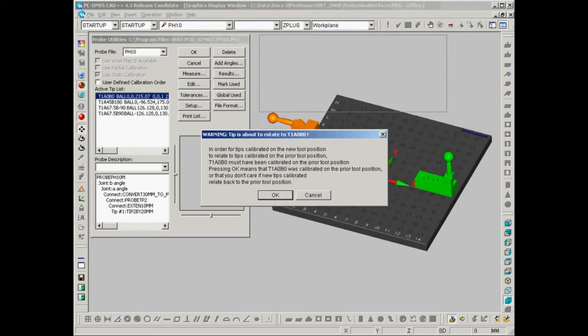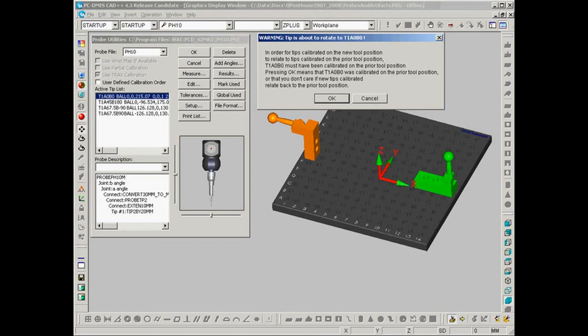Now this is what this dialog means. In order for tips calibrated on the new tool position to relate to tips calibrated on the prior tool position, tip A0B0 must have been calibrated on the prior tool position. And we've just done that. So this is the dialog that creates that relationship, or at least affirms the creation of the relationship between the green sphere and the orange sphere. We'll just select OK here.